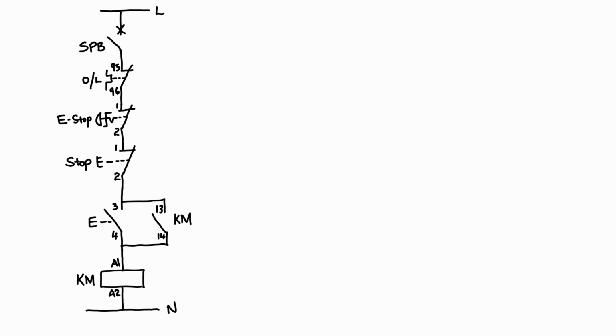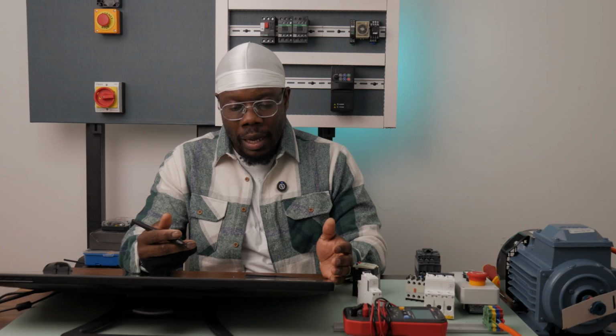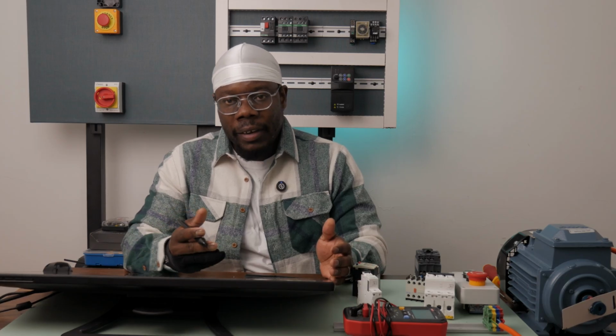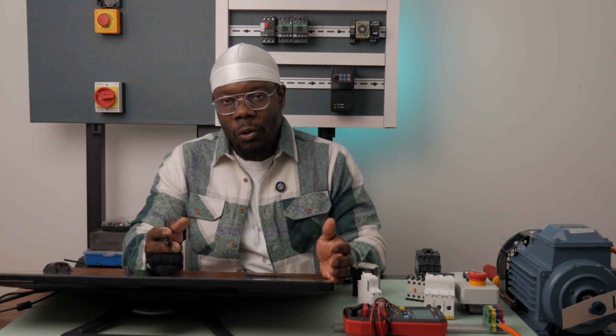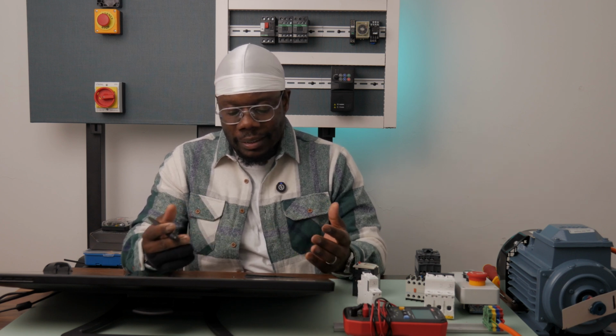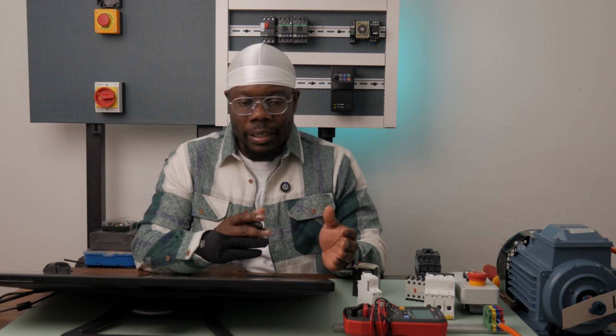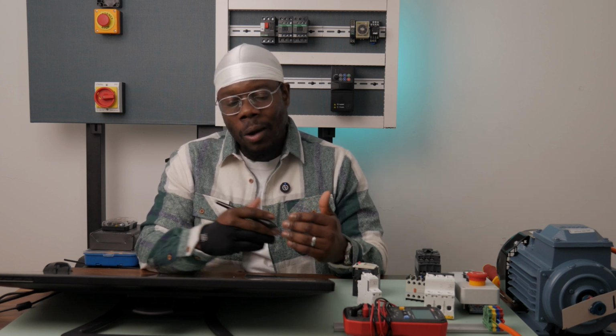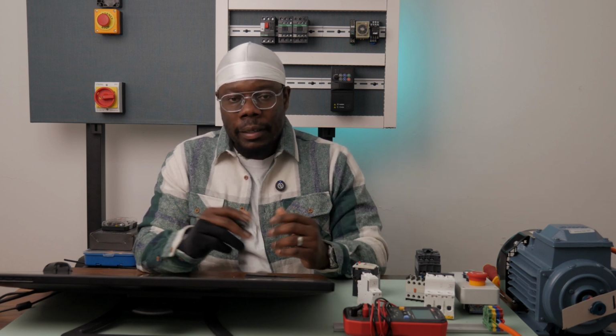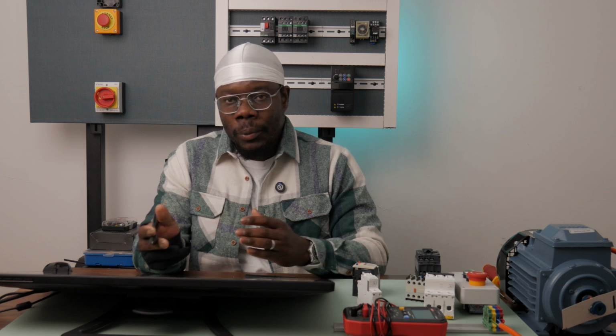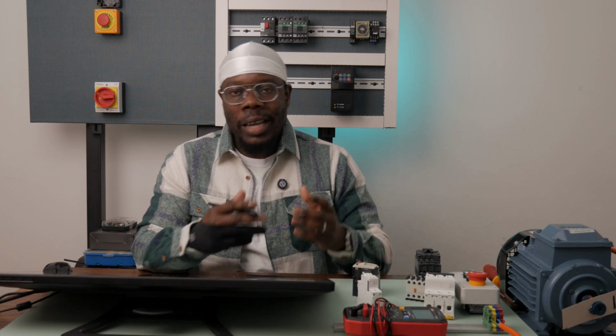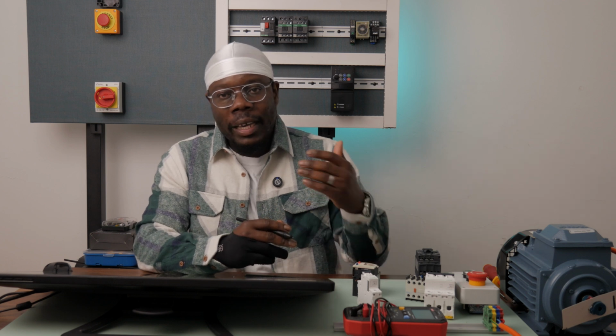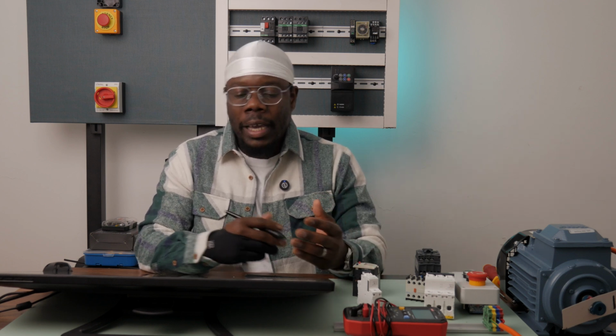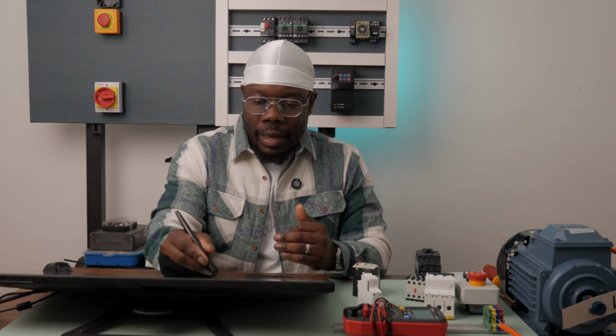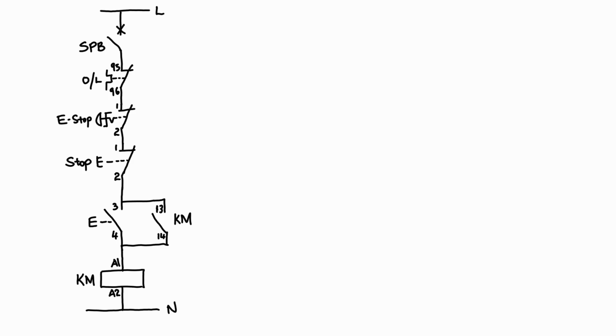If you are doing this for a real circuit, it might be worth it to actually indicate which phase you are getting your control voltage from, because if it's a three-phase system, then you want to know whether you are taking your control from L1, or from L2 or L3. And I know that there are different colors for different countries. Some countries use red, white, and blue. Some use red, yellow, and blue. So are you getting your control from the red phase, or the yellow phase, or the blue phase? Always indicate. But here I just put live at the top. So it should be sufficient for our practice.